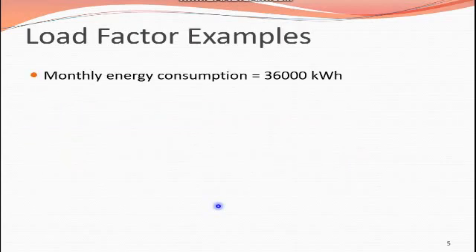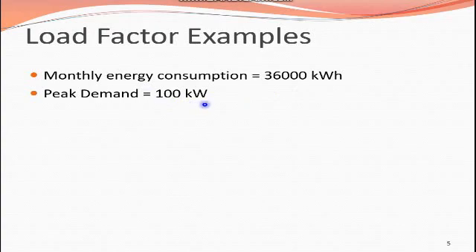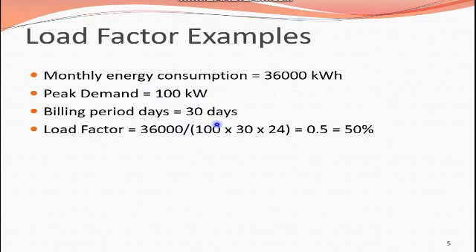Here is an example about load factor. Monthly average consumption is 36,000 kilowatt-hours, peak demand is 100 kilowatts, and the billing period is 30 days. Load factor equals average demand divided by maximum demand. The average demand is 36,000 divided by (30 days × 24 hours), and peak demand is 100, giving a load factor of 0.5.